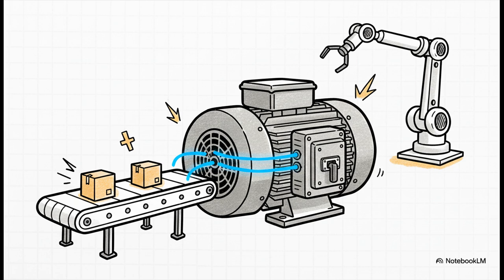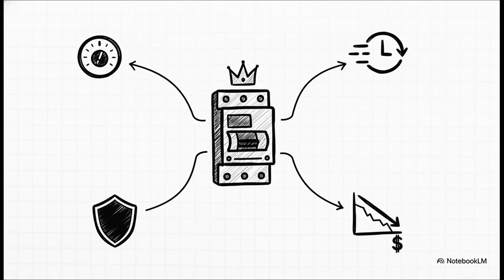In a situation like that, one of these is the obvious choice. Yeah, in these places, the circuit breaker is king, no question. Because they're adjustable, engineers can fine-tune the protection to match exactly what a big motor needs as its load changes. And the fact that you can reset them in seconds, sometimes even remotely from a control room, that's absolutely critical when every minute offline is money down the drain. So that higher upfront cost pays for itself over and over in reliability.